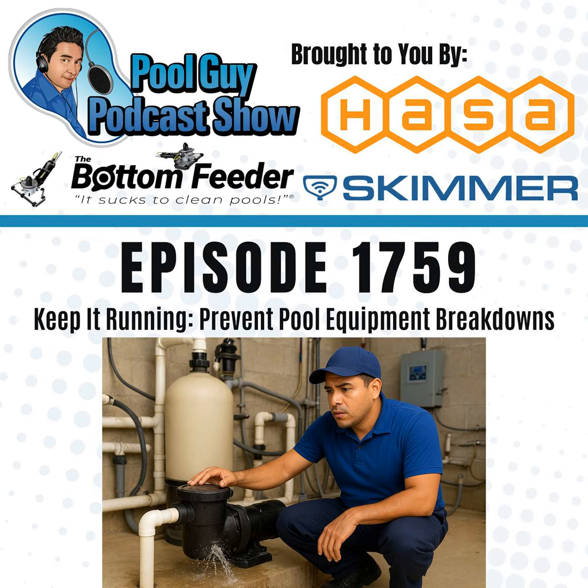It's embarrassing, but I've checked the heater thoroughly for a long time, and then I realized that the customer had the gas valve turned off. It was one of those, oh yeah, moments where now I check that first. But igniters are usually a problem. The error codes are all a little different on the heaters, so they'll give you an error code, usually letting you know what that is, and you can look it up.